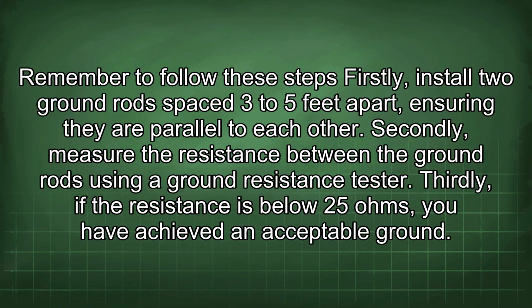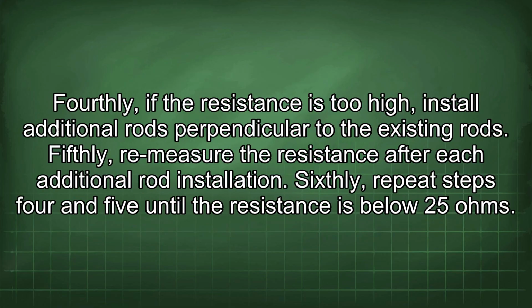Firstly, install 2 ground rods spaced 3 to 5 feet apart, ensuring they are parallel to each other. Secondly, measure the resistance between the ground rods using a ground resistance tester. Thirdly, if the resistance is below 25 ohms, you have achieved an acceptable ground. Fourthly, if the resistance is too high, install additional rods perpendicular to the existing rods. Fifthly, remeasure the resistance after each additional rod installation. Sixthly, repeat steps 4 and 5 until the resistance is below 25 ohms.